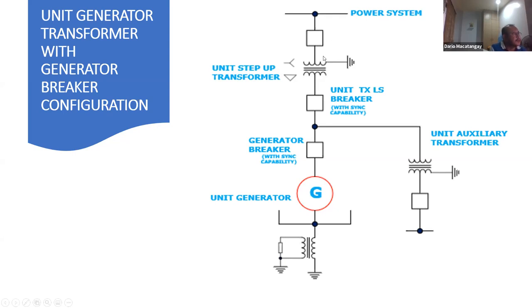Okay. Once you lose a huge amount of load, the generator and the turbine might increase in speed, overspeed, or you can trip the generator and the turbine altogether. So if you have good load rejection capability, then once you lose this transformer, you can still maintain the generator running and power the unit auxiliary transformer. That's a good thing, right? Even with the outage of this transformer, you can easily restart the generator, and it's a more economical operation, right?